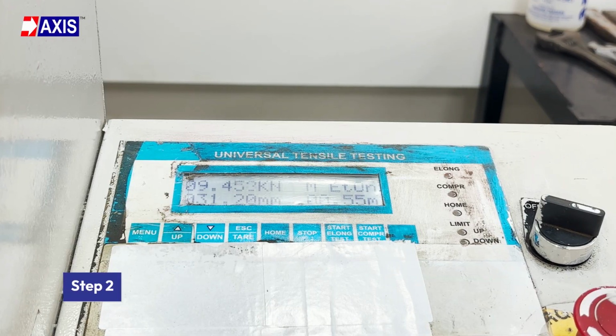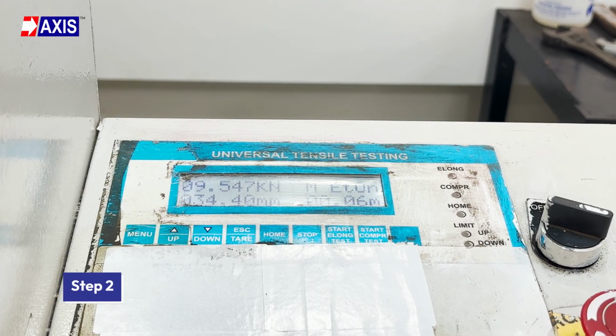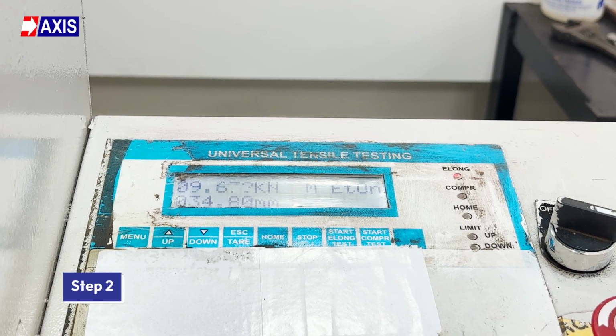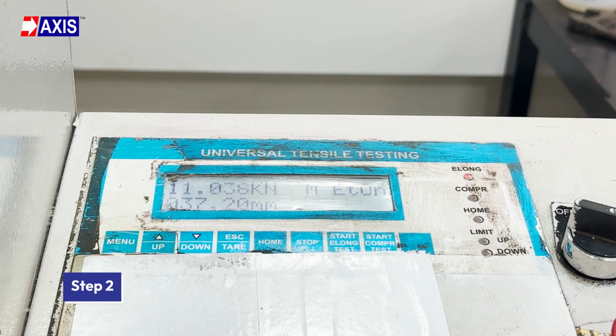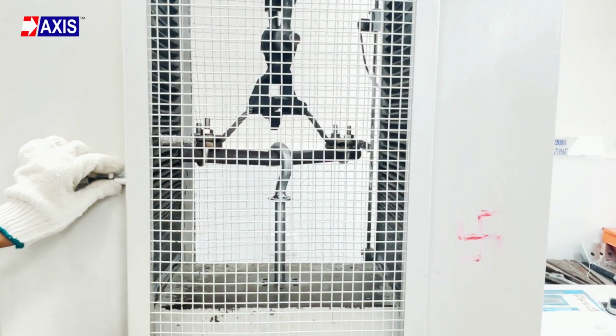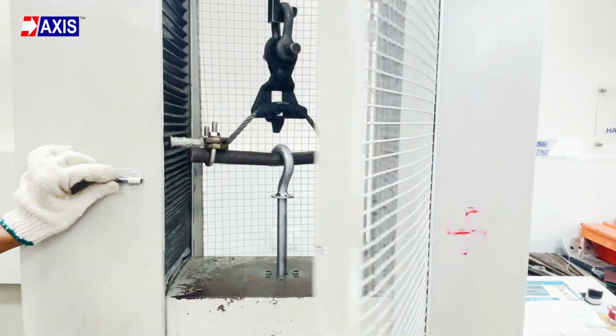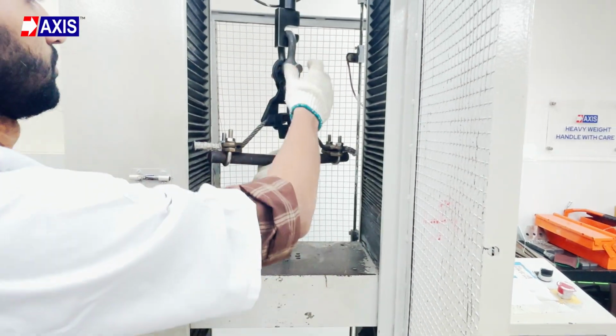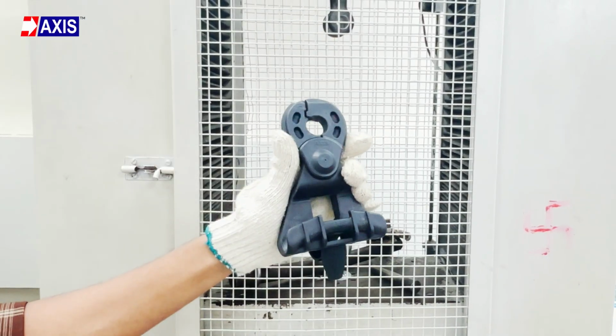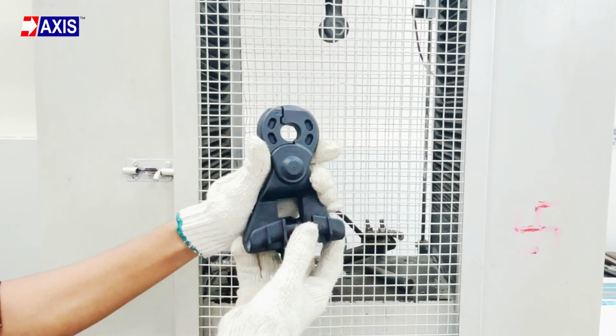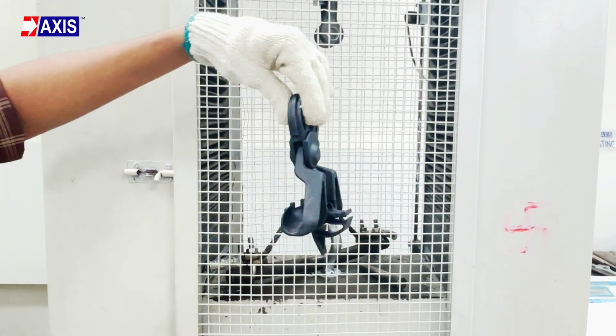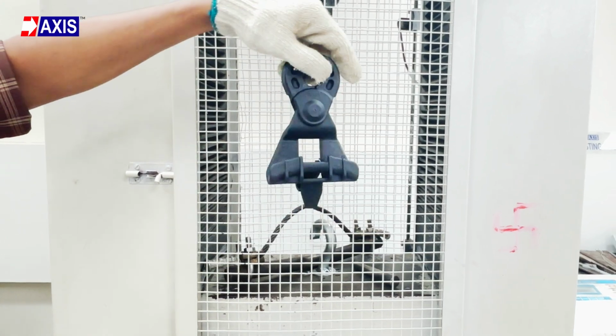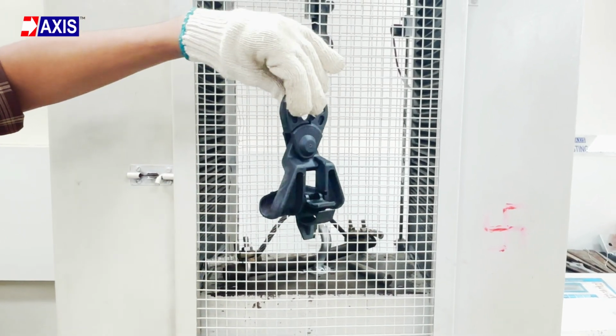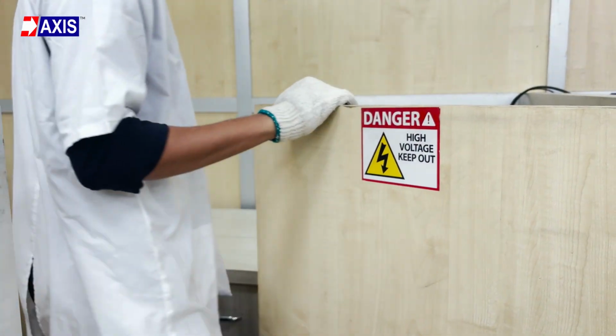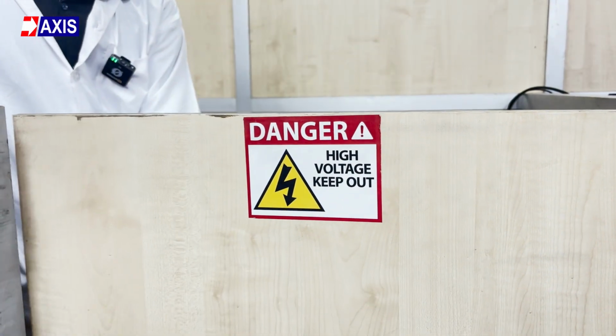Step 2. Apply the load gradually up to 9.6 kN. Hold for 1 minute and then take it up to 12 kN. The clamp passes the test if there is no visible deformation, cracking, or fracture. As you can see, the Axis suspension clamp has completed the test without any failure because there is no visible deformation, cracking, or fracture. I hope you now have a clear understanding of how to test your suspension clamps.